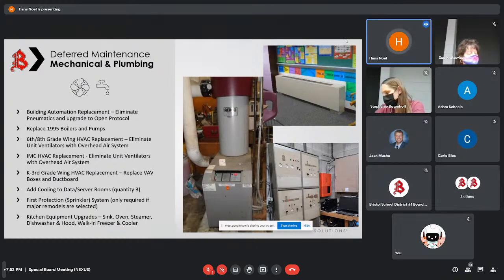MS6, 7, 8, and 9 all serve the oldest wing — what I call the K through 3rd grade wing. There are a couple different options here. At minimum is MS6, where we'd just replace the VAV boxes — small unitary devices at each room that control individual room thermostats. They don't go to the big air handling unit, the source equipment, which was replaced as part of the HVAC wing. I think once it was built there was a little extra money, if I remember right — I was actually walking through the building then and was told they were doing that work. So that's why we're not proposing to replace that air handling unit, because it is newer.